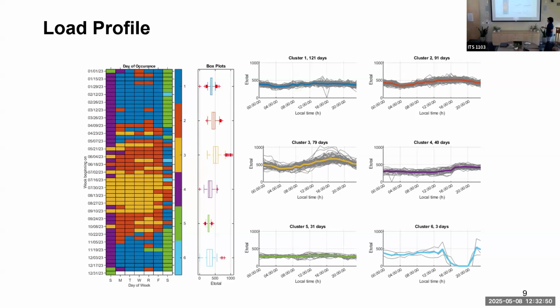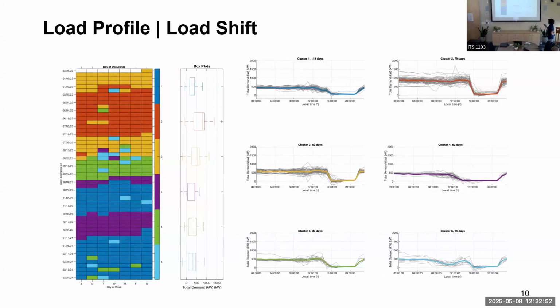And what we want to do with some of these is what's shown here. We want to have the facility operate as consistently as possible during those off-peak periods. And during those on-peak periods, so maybe here 4 to 9, I know this is a little difficult to read, but this is 4 o'clock, this is 8 o'clock, so this is 9 p.m. in all of the different clusters. So you want the facility to be as low as possible during the 4 to 9 period. But the second thing we also want is not to spike that demand during off-peak periods.